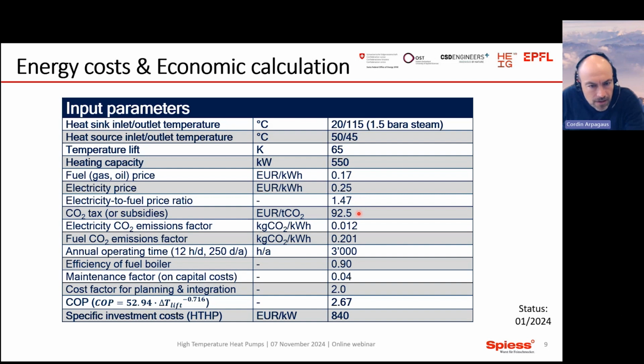Then also CO2 tax, and a CO2 emission factor for the electricity, which was assumed quite low, like renewable electricity. They have PV on the roof and also have a good contract for the electricity. Then the gas has its emission factor, and the operating time was assumed to be 3,000 hours per year. Efficiency of the boiler 90%, maintenance factor 4% on the capital cost, and a cost factor for planning and integration of 2. With the temperature lift of 65 Kelvin, a COP of 2.67.